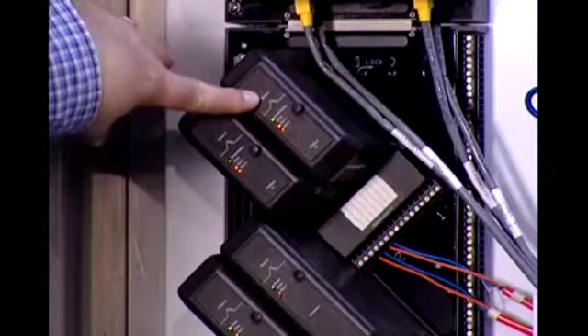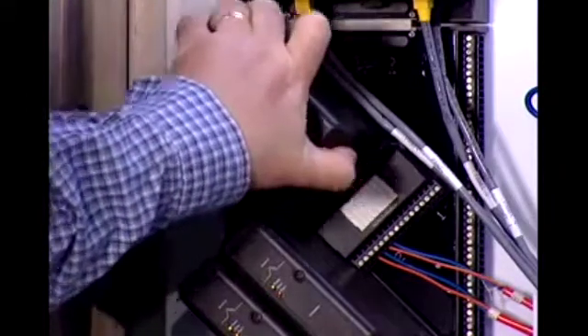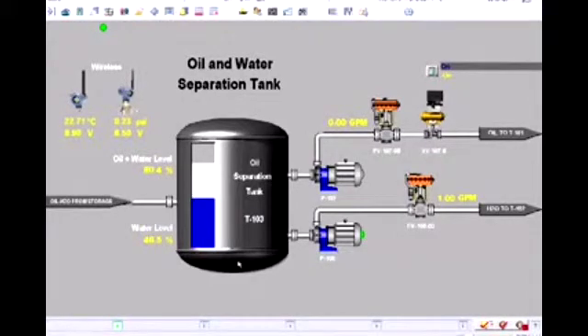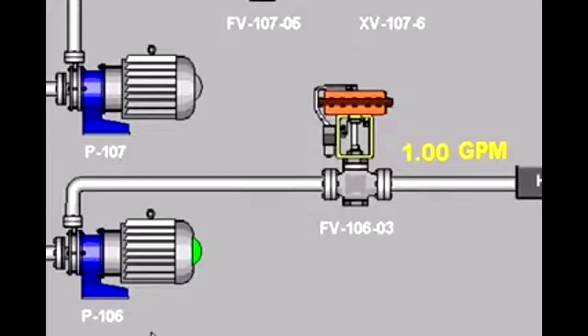What I'm going to do is pull the active card and we'll notice that the backup card is no longer blinking. It took over control of the Fieldbus segment and everything is still running fine. The loop is running at one gallon per minute and we can see the flow on the screen.